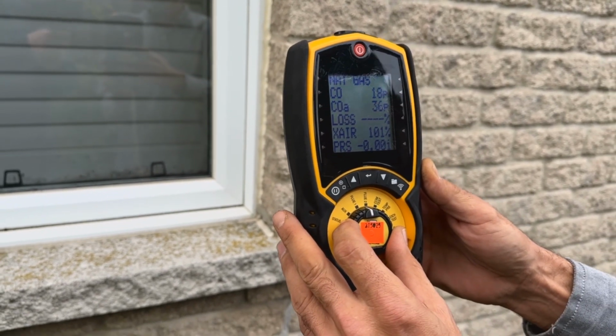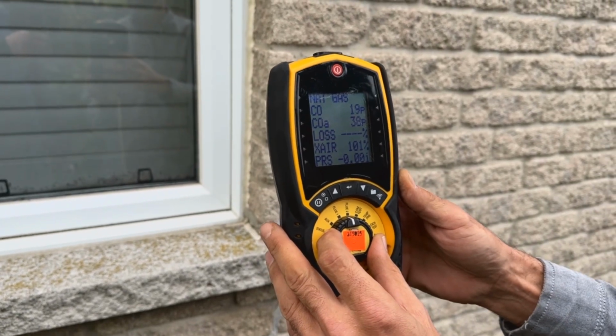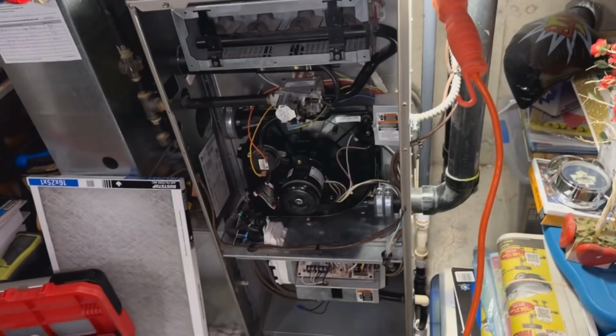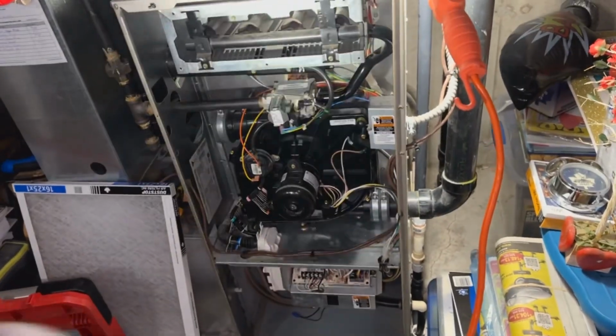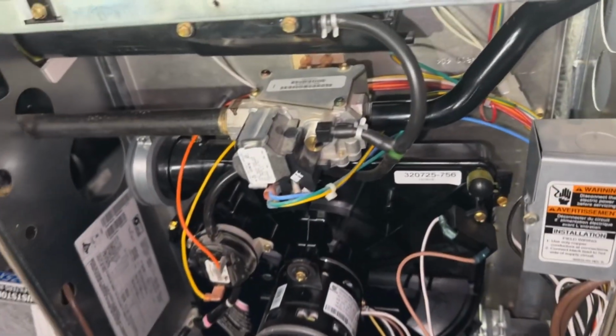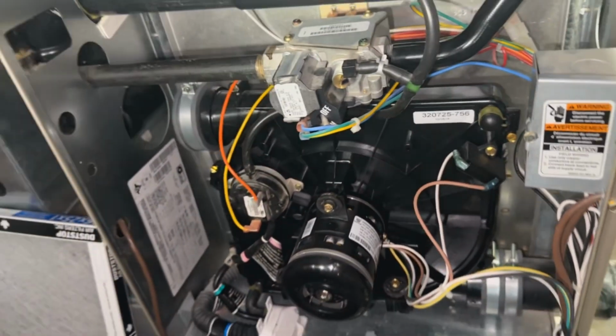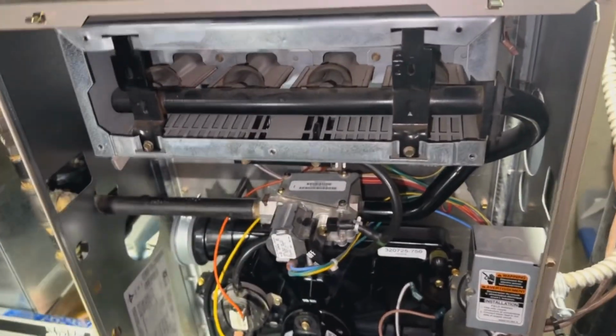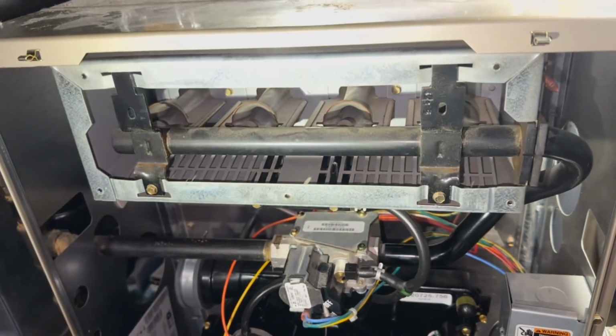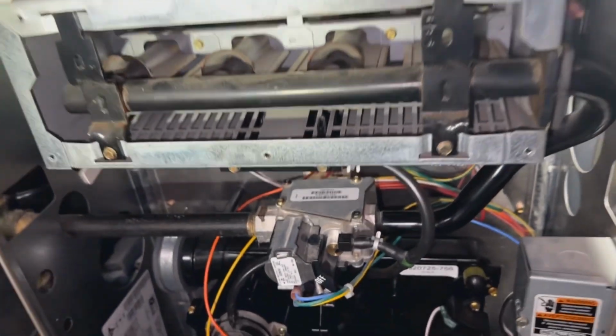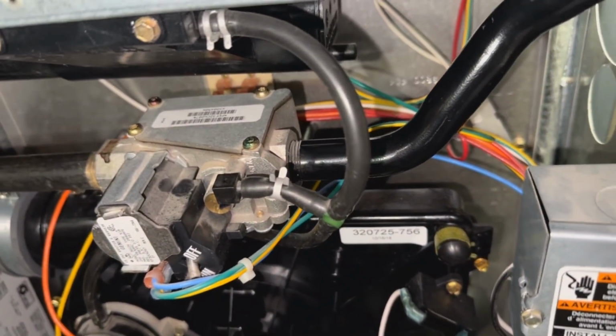Now, do you want to go do a quick check on your pressures? Let's go double check the gas pressure. So now that we're back inside, when you're checking gas pressure, you tie into the gas valve here. There's a little port on the side. There are two different ways to do it. Because my particular furnace has an enclosed burner box, you either take the door off or you have to tie into that pressure tube.